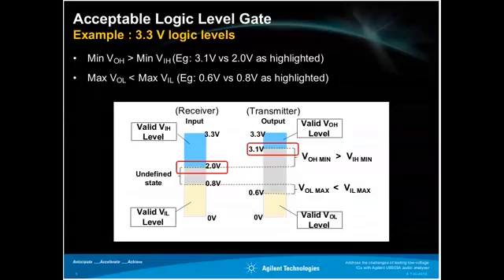Normally, digital receiver high voltages are less than the transmitter high voltages, but digital receiver low voltages are greater than the transmitter low voltages. The valid input high voltage level usually ranges from 2 volts to 3.3 volts, depending on the device you are testing.